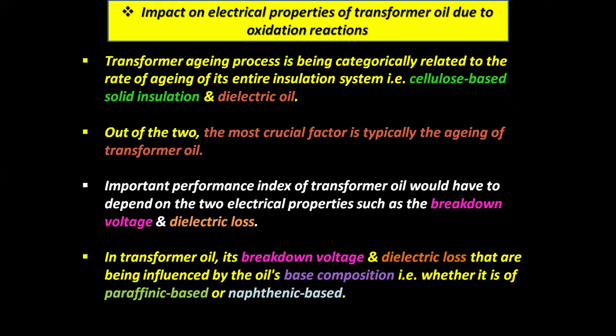Let's start with the impact on electrical properties of transformer oil due to oxidation reactions. The transformer aging process is categorically related to the rate of aging of its entire insulation system, that is, cellulose-based solid insulation and dielectric oil. Out of the two, the most crucial factor is typically the aging of transformer oil.